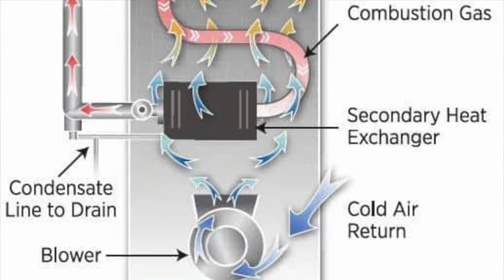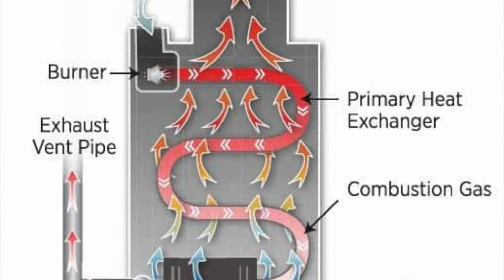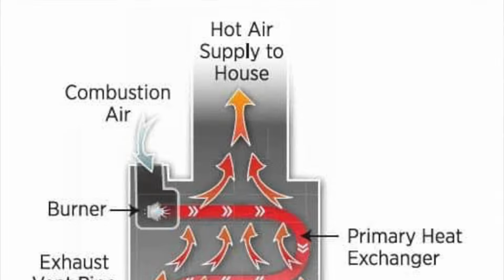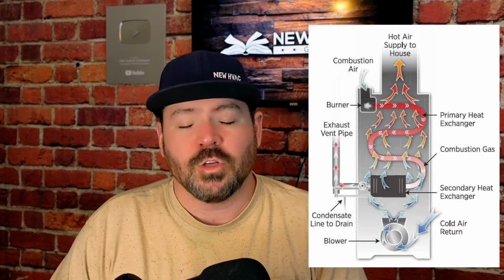Of course, it's harder on the fan motor trying to push more air through a smaller duct, but it's also harder on things like the heat exchanger and other components that have to do with the combustion burning of gas in that system. Less airflow across those components can mean things get hotter than they're supposed to, than they were designed for, and again, cause more failures.